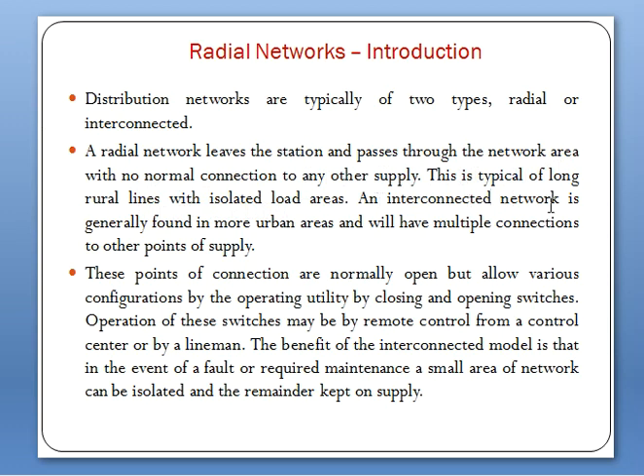An interconnected network is generally found in more urban areas and will have multiple connections to other points of supply. These points of connection are normally open but allow various configurations by the operating utility by closing and opening switches. Operation of these switches may be remote controlled from a control center or by a lineman. The benefit of the interconnected model is that in the event of a fault or required maintenance, a small area of network can be isolated and the remainder kept on supply.